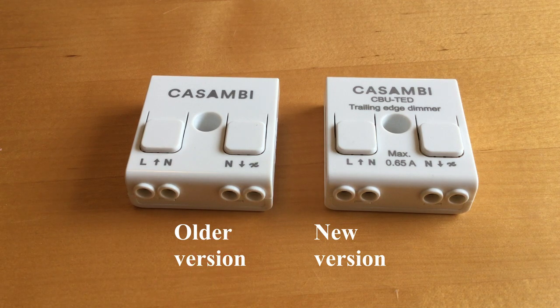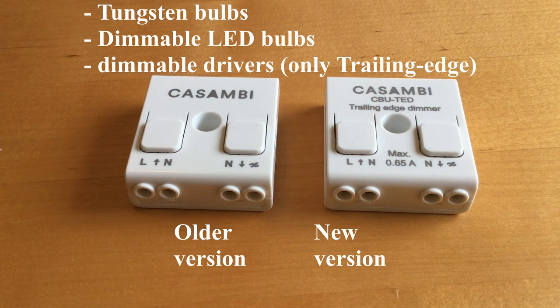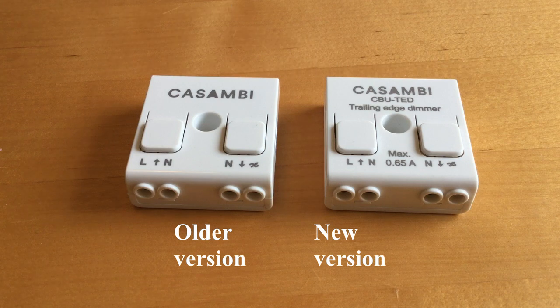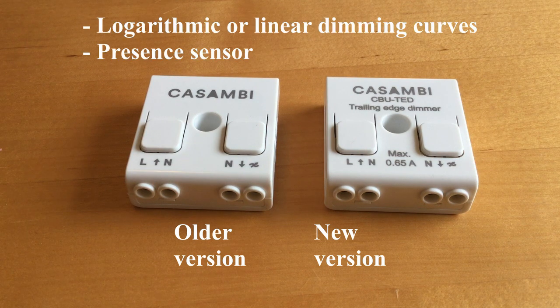The type of load that you can attach to these are things like dimmable LED drivers or incandescent or tungsten bulbs, things like that. There are two types of dimming curve available for the TED, a logarithmic and linear, and they can be changed in the Casambi app. There's a third option available which allows the TED to be used as a presence sensor, and that's something we'll talk about later on in a separate video.